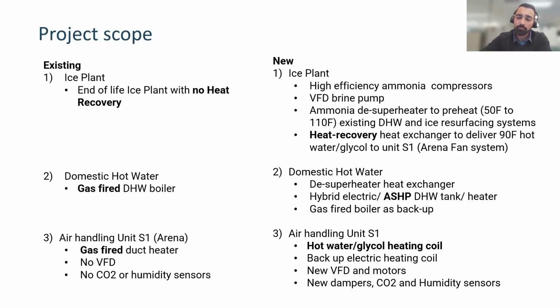For the air handling units, based on the recovered waste heat, we were able to supply that to the arena air handling unit, and that was through a hot water glycol heating coil. And that will basically be sufficient for the winter months, but whenever we want to supplement that, we will rely on the electrical heating coil that we will have in place, and that would necessarily be the backup. Also, and I speak for both of our fan systems right now, we don't have VFDs. The dampers are not controlled by the BAS. We don't have CO2 sensors or temperature and humidity sensors, and we are adding them as part of this retrofit. We can go to the next slide.